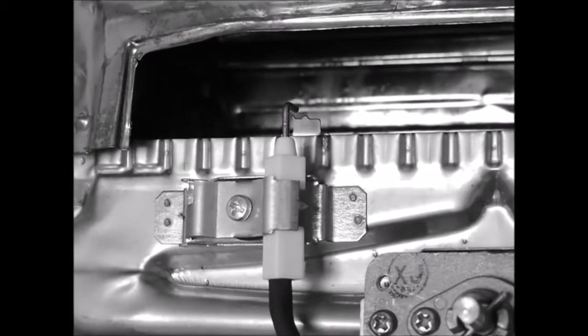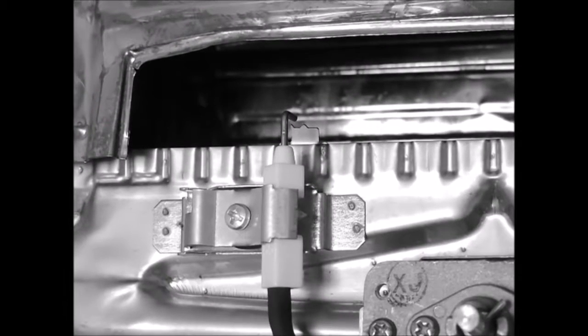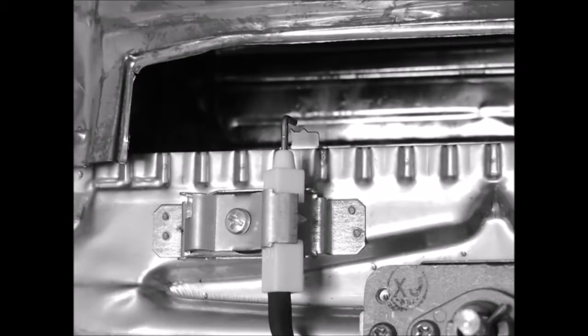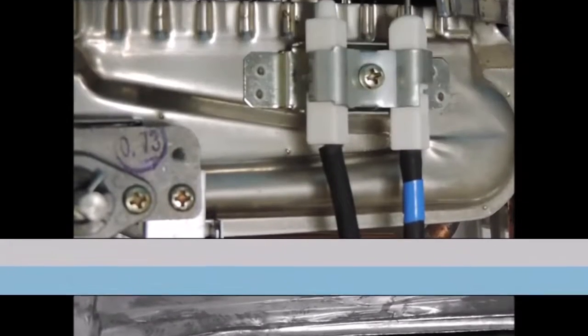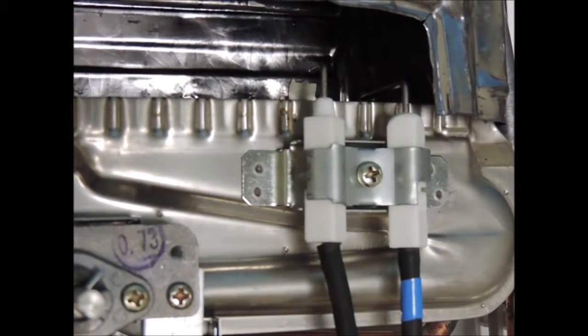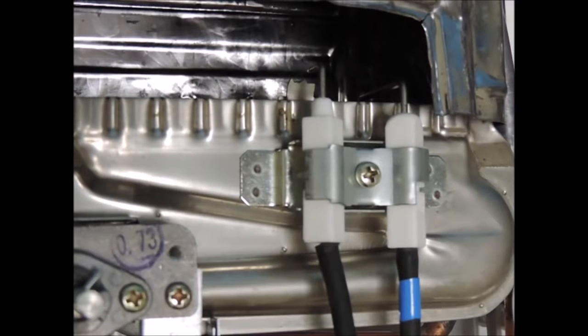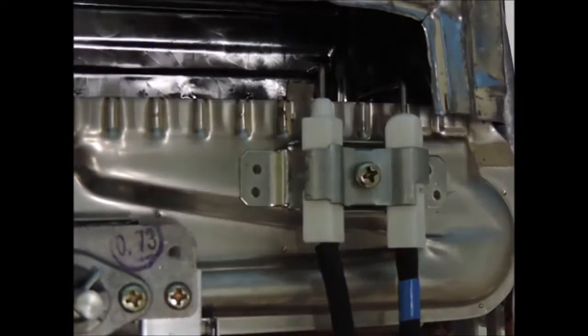Next, look at your igniters to make sure you are getting spark at the tip where it meets the top of the burner assembly. If you hear the clicking but do not see the spark at the tip of the igniter, it is possible that the spark is occurring towards the bottom by the wire, and you will need to push the thick black wire that connects the igniters further onto the connection pin.